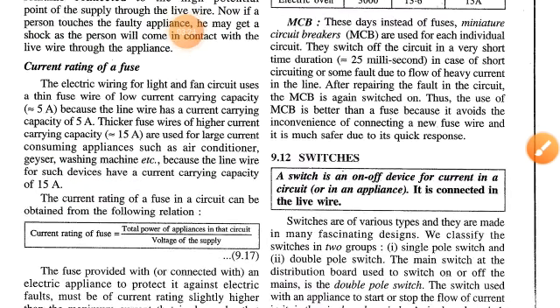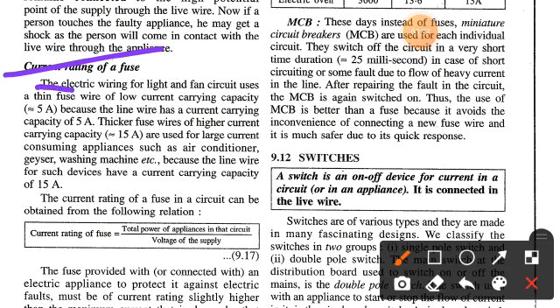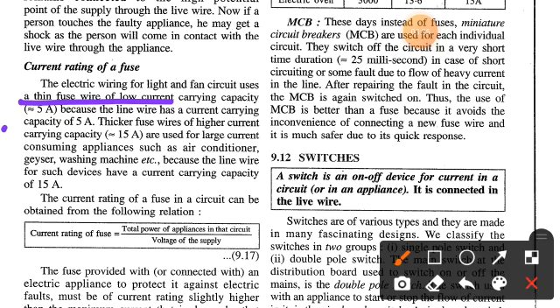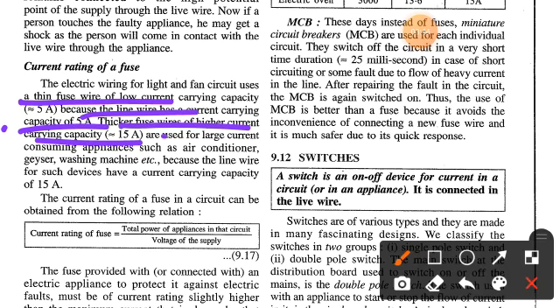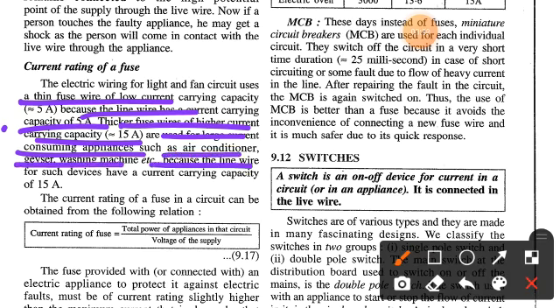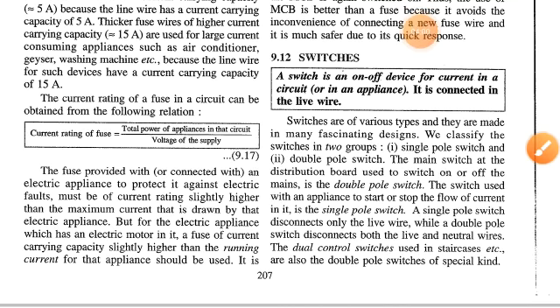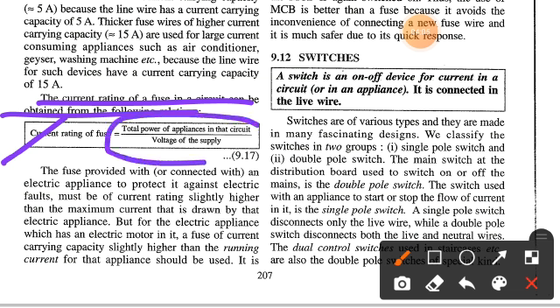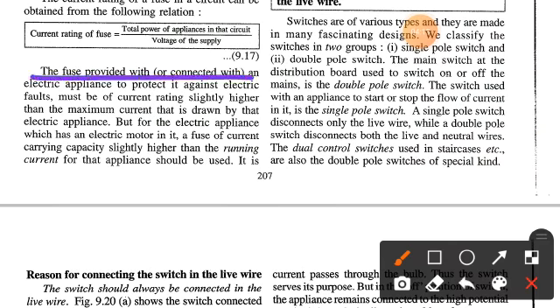Regarding the current rating of a fuse: the electric wiring for a light and fan circuit uses a thin fuse of low current carrying capacity — approximately 5 ampere — because the line wire has a current carrying capacity of 5 ampere. Thicker fuse wires of higher current capacity of approximately 15 ampere are used for large current-consuming appliances such as air conditioners, geysers, washing machines etc., because the line wires for such devices have a current carrying capacity of approximately 15 ampere. The current rating of the fuse equals the total power of appliances in the circuit divided by the voltage of the supply.